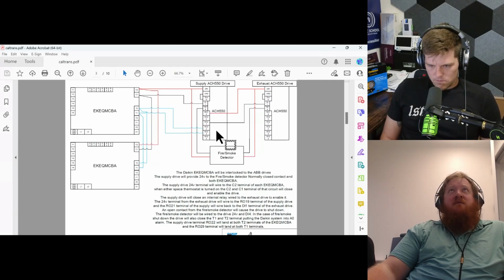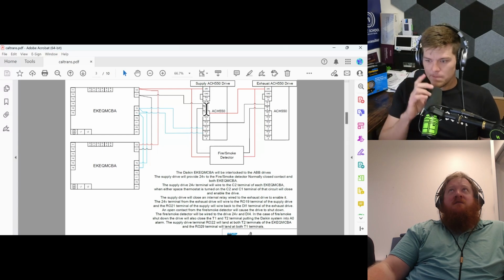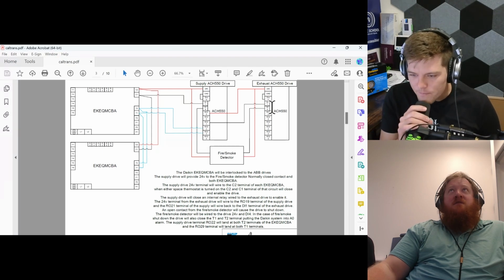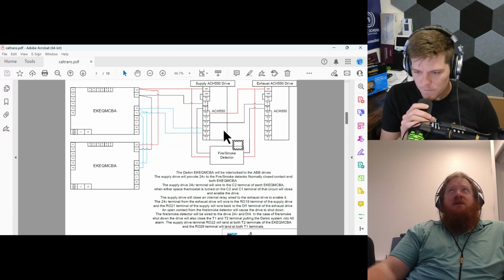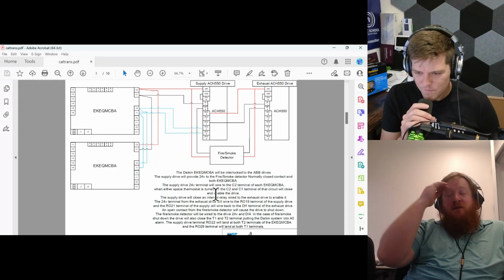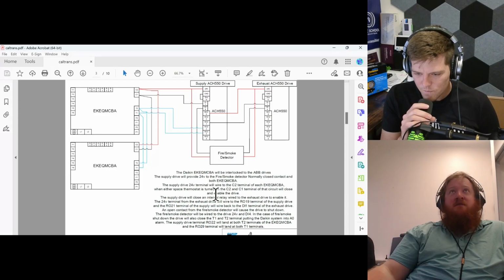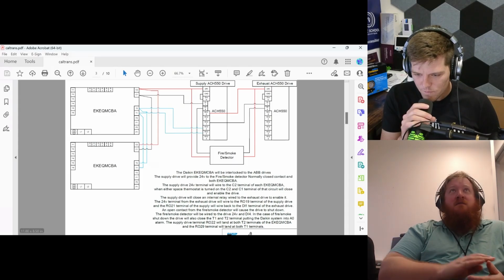So here's a dual kit, dual VFD, exhaust and supply VFD, one smoke detector, and this is how it worked. We use our contacts on the VFDs to shut them down or start them, and we use our relays to make it work. Here's the sequence of how this was designed and how it operated.